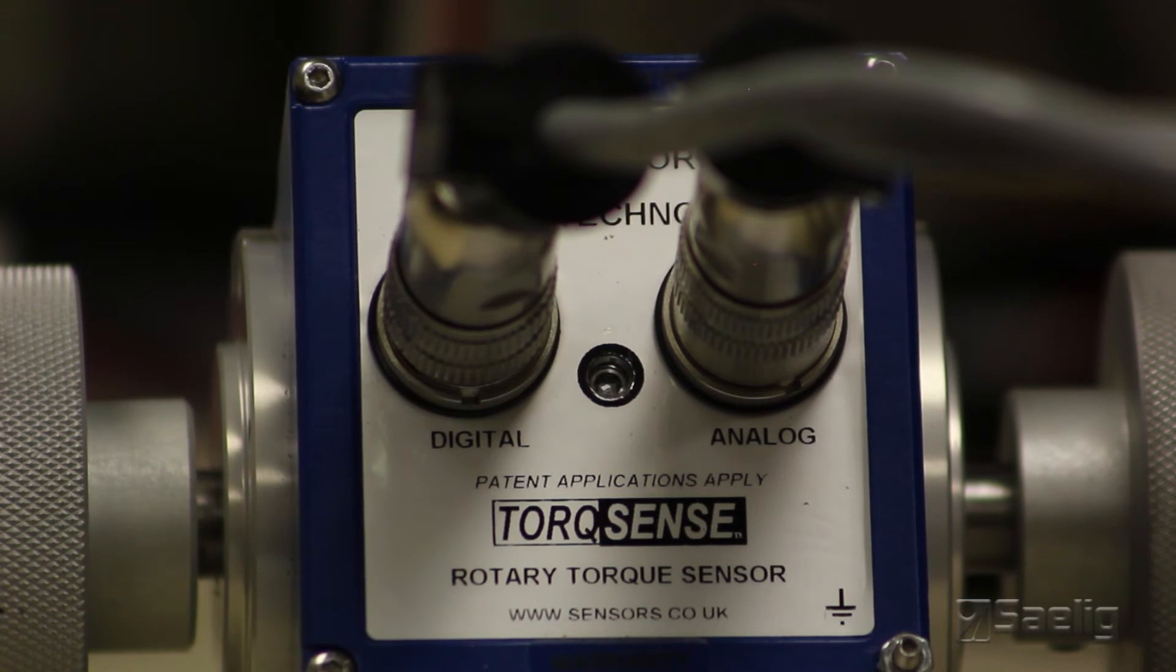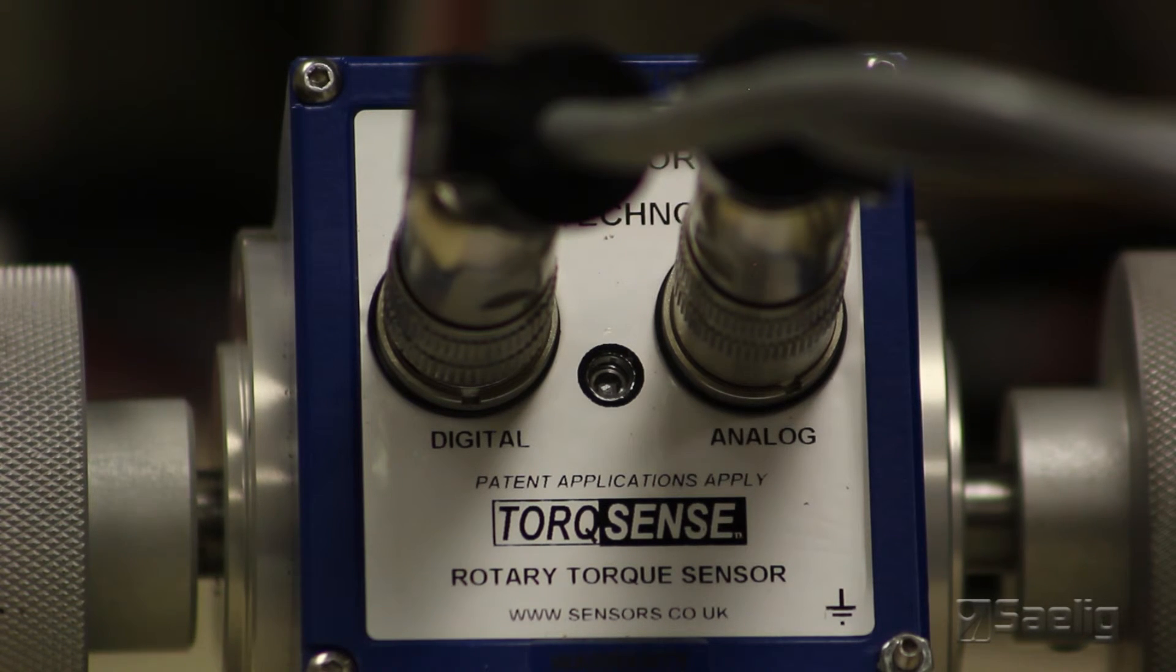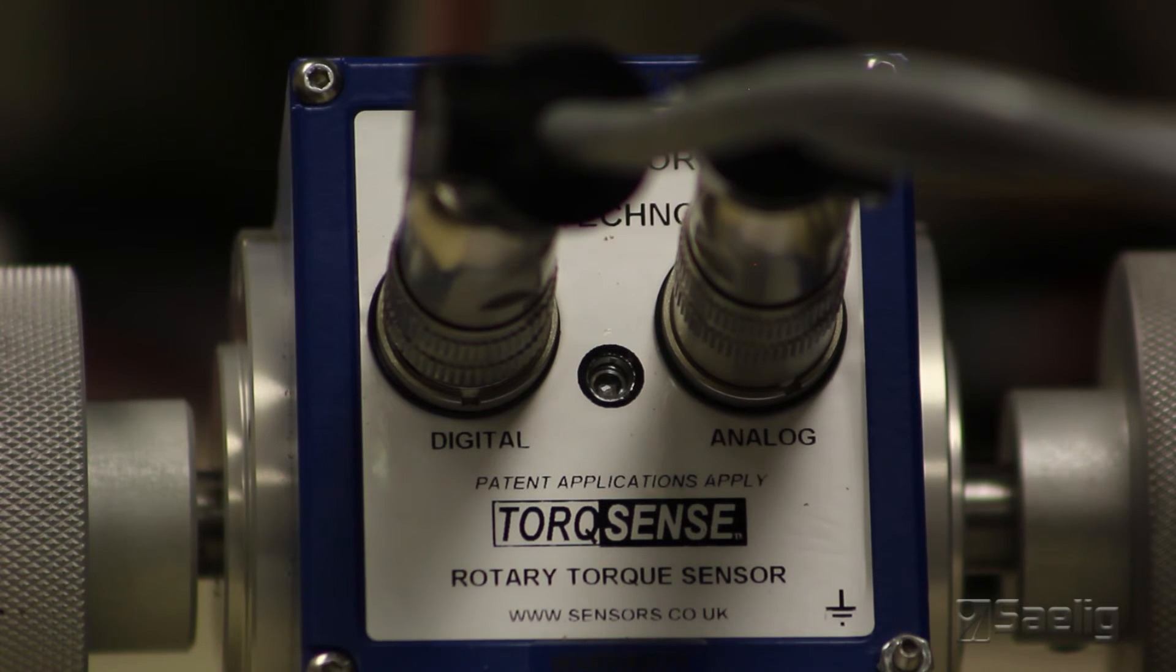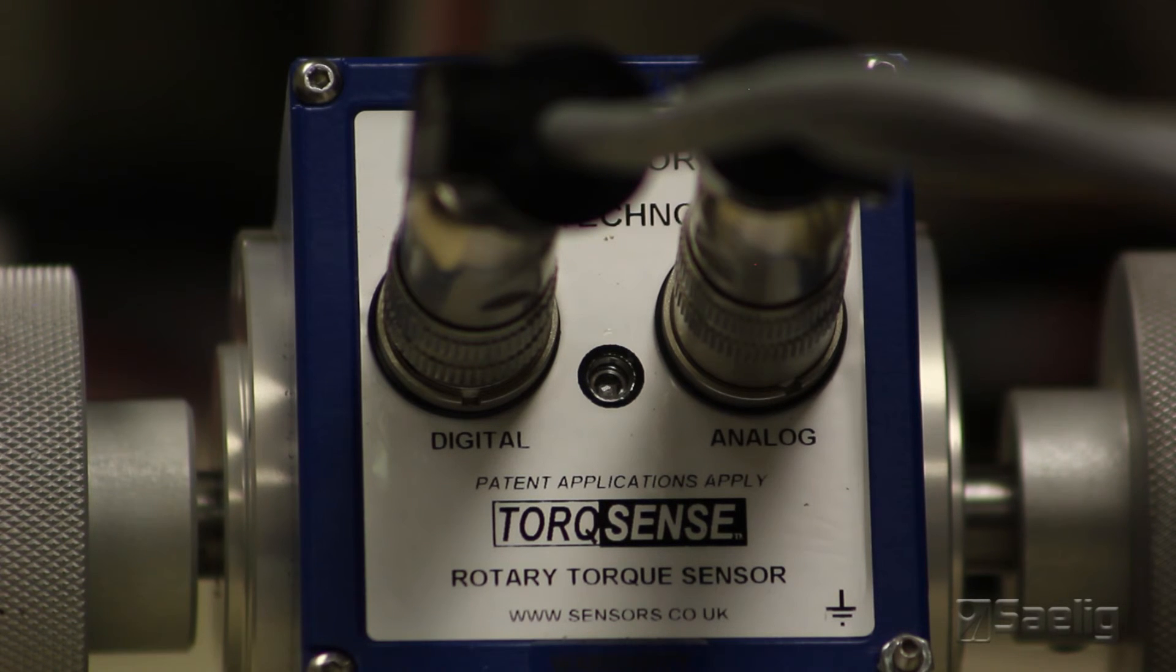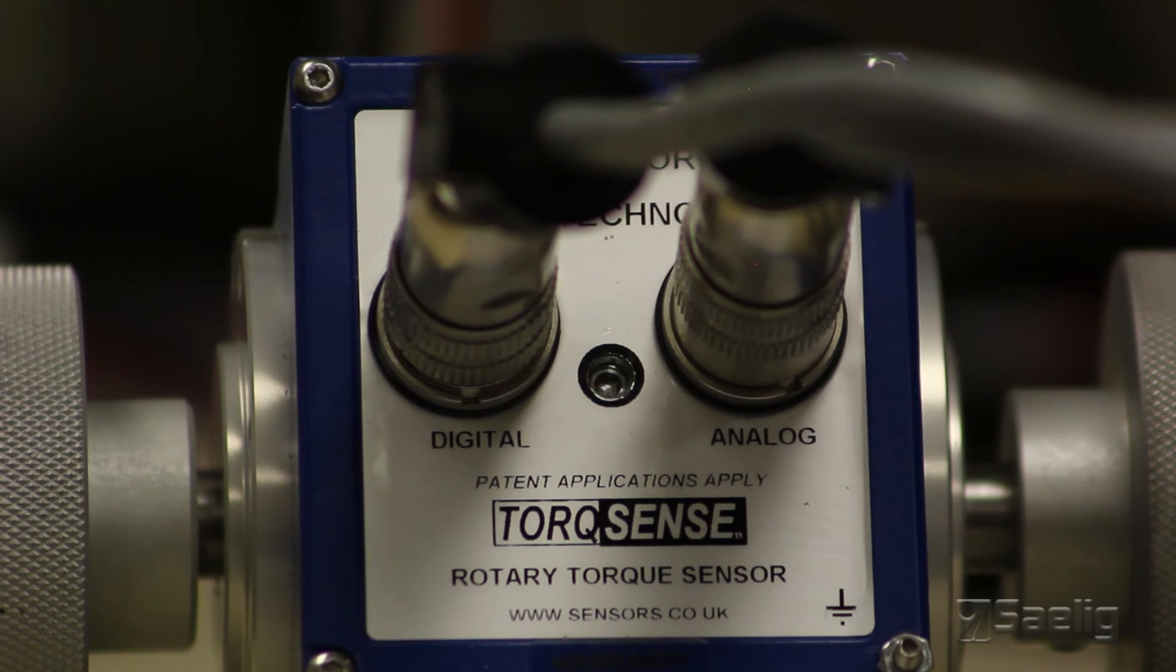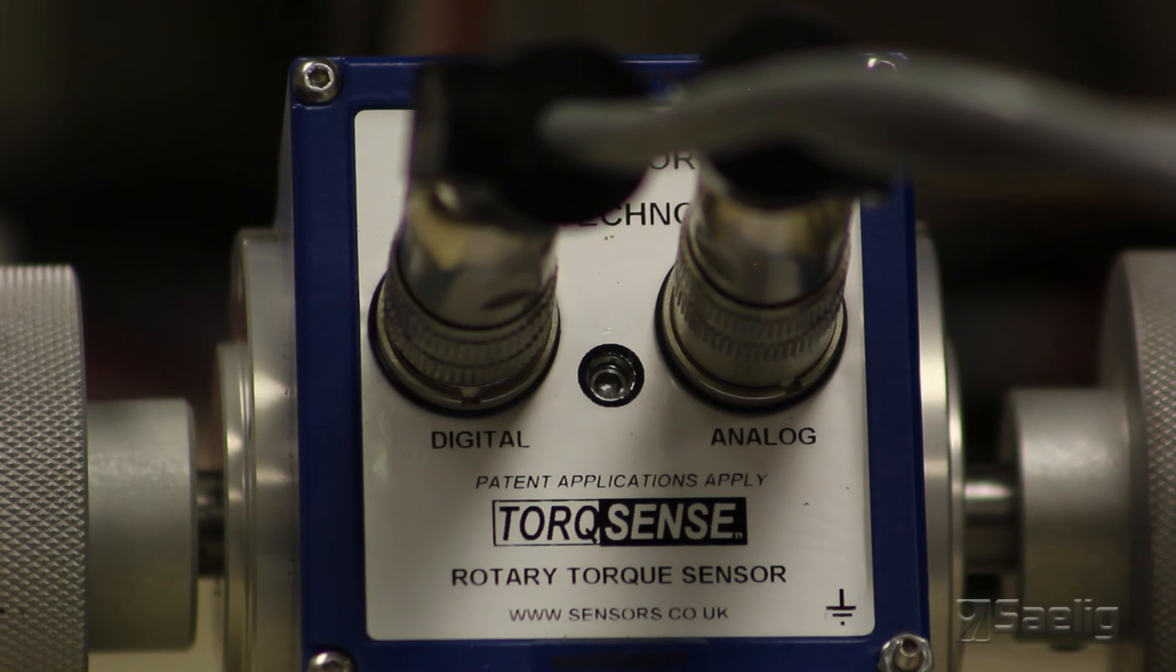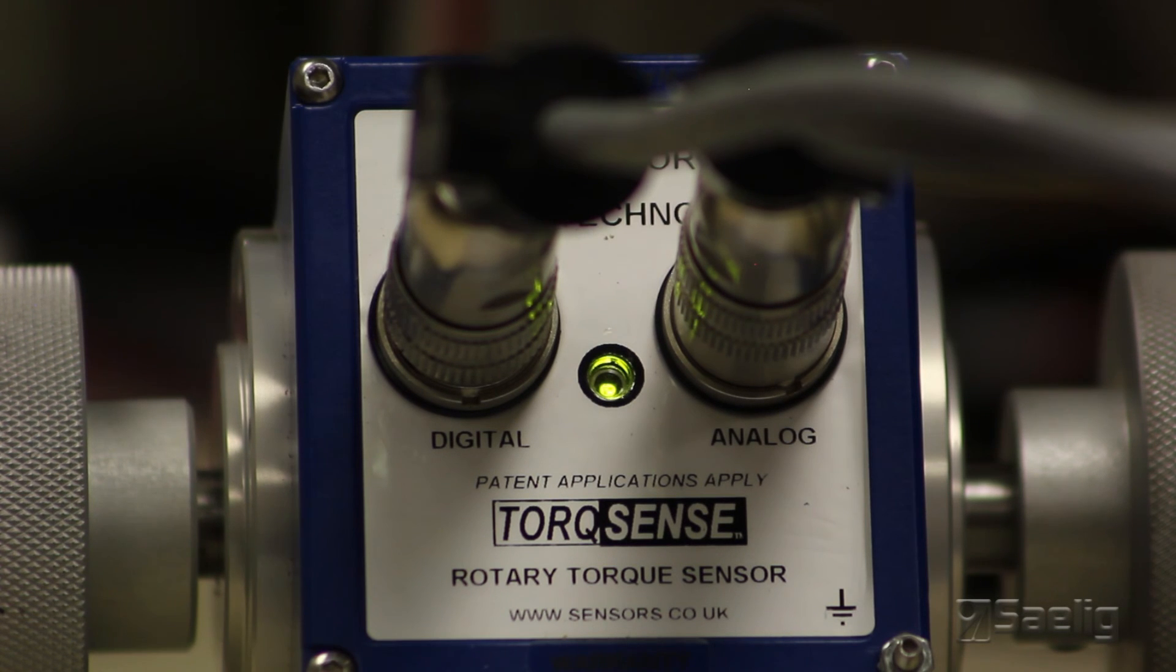When you first turn the transducer on, it runs through a power-on self-test. It's got a simple two-color LED in the front of it, and it starts out a little bit red, and then it goes through its power-on self-test. It blinks several times and should end up with a steady green light, like this. Here it goes. It's completed its power-on self-test successfully. It's operating, and there's no faults found in the transducer.